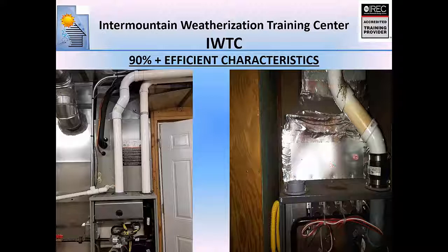Now, here's a job performed by Weatherization where they got lazy and they only ran the exhaust pipe up and out and they left the intake wide open. Now note, there's not a sealed combustion chamber here like this guy. The sealed combustion chamber can actually be the front door going on it. And remember in the pictures before, the front doors on 90 plus have no louvers. That's because the combustion air comes through here.